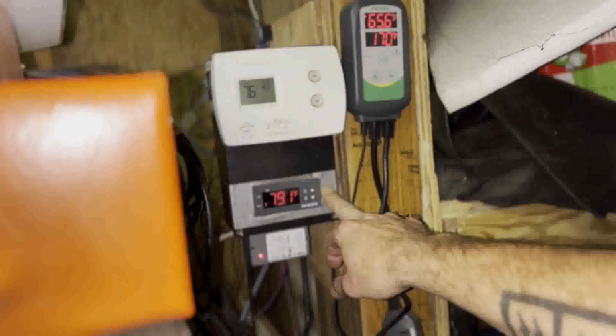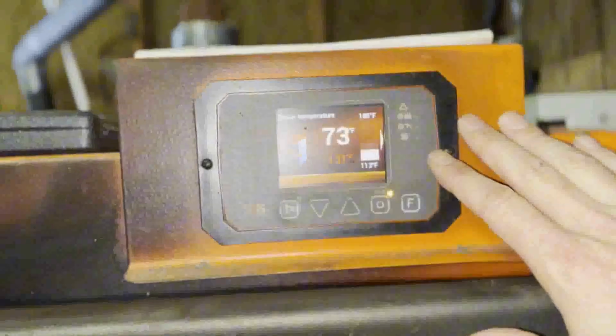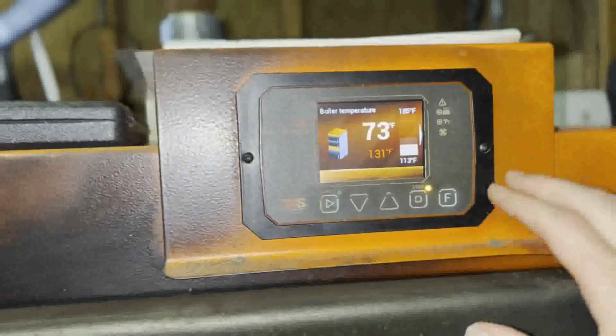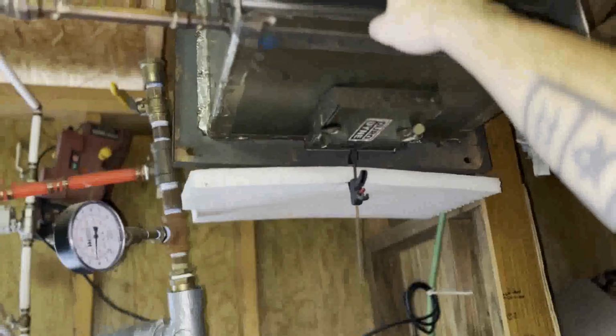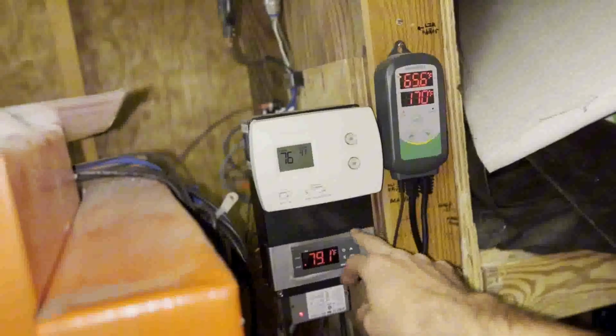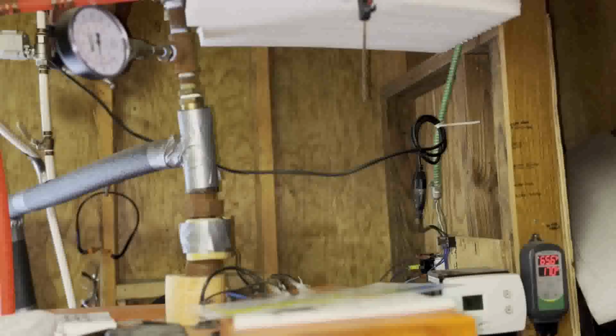And then this right here is an additional safety. If the water gets too hot, this has its own circuit where it'll lock out the blower. I'm not going to let it get any hotter. But if it gets that hot or hotter, this is actually going to bring on this heating unit here, this unit heater, which is going to open that valve. It's going to dump the heat. So if this gets an over temp situation, this is going to bring on this heat, and it's just going to dump the heat here in the house. So, extra safeties that I wanted to put in, just additional safeties beyond what this is.